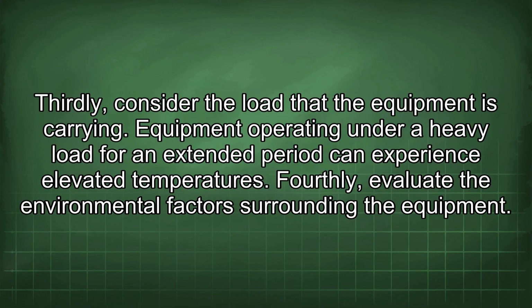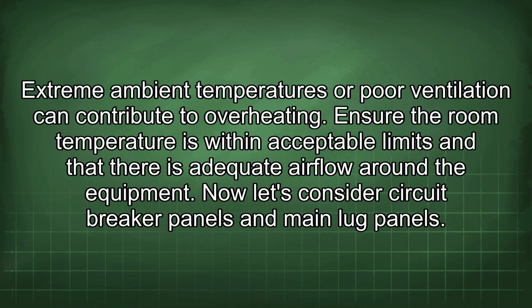Thirdly, consider the load that the equipment is carrying. Equipment operating under a heavy load for an extended period can experience elevated temperatures. Fourthly, evaluate the environmental factors surrounding the equipment. Extreme ambient temperatures or poor ventilation can contribute to overheating. Ensure the room temperature is within acceptable limits and that there is adequate airflow around the equipment.